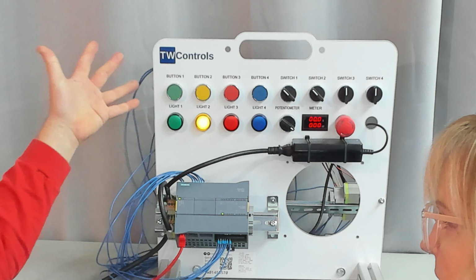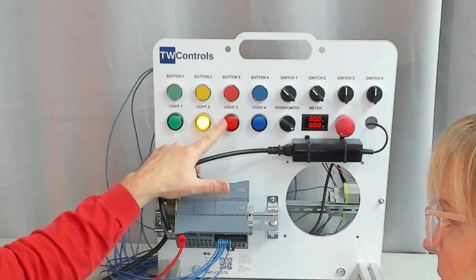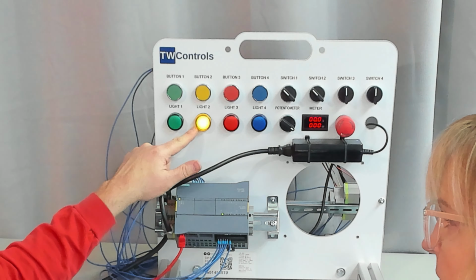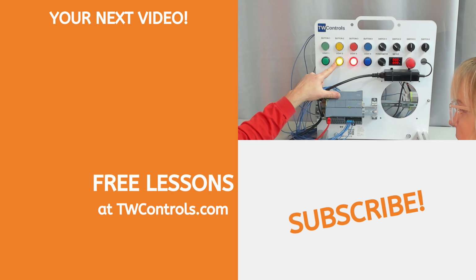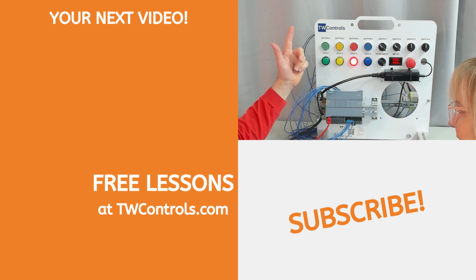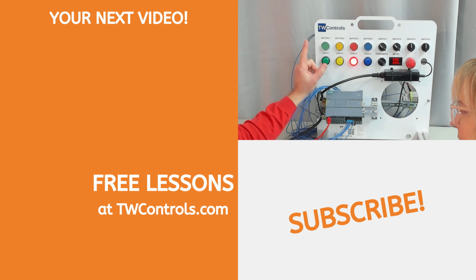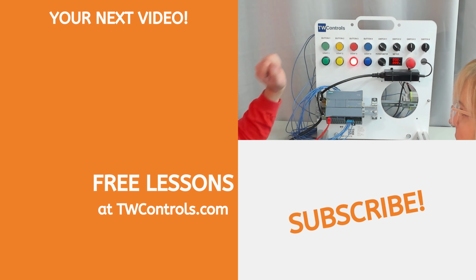So I'll let off the button. Our timer is going to start timing, and we'll get a hint of that by this turning on in a second, but mainly we'll focus on this. 10 seconds after I let off that button, it'll go false. So on a TOF, the Q bit will be true whenever the instructions preceding the TOF are true, or it's been false for less than the preset time.